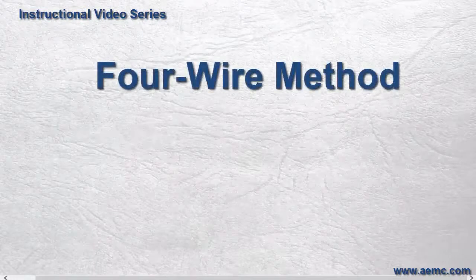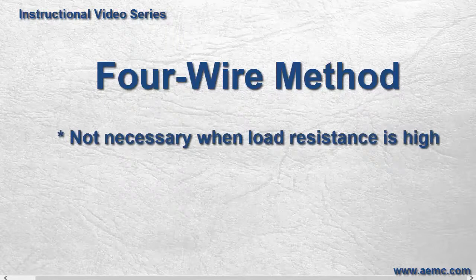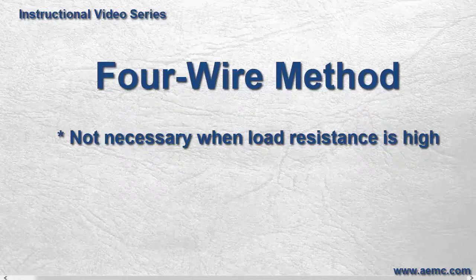Note that the four-wire method is not suitable for all applications. For example, when the load resistance is high, the resistance in the probes is relatively smaller as a percentage of the overall resistance and therefore does not introduce an unacceptable margin of error.